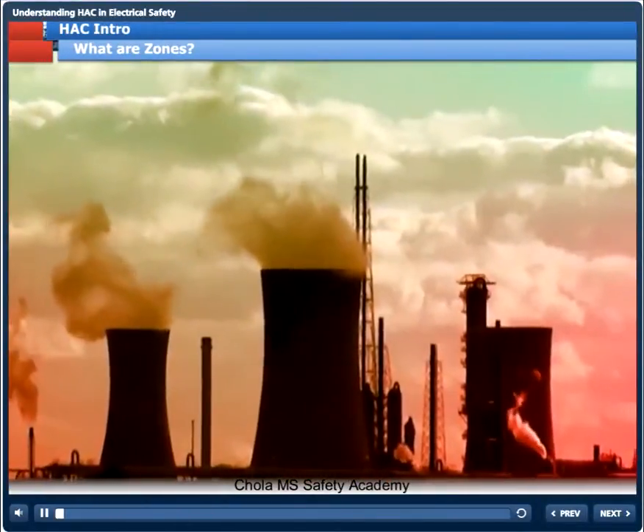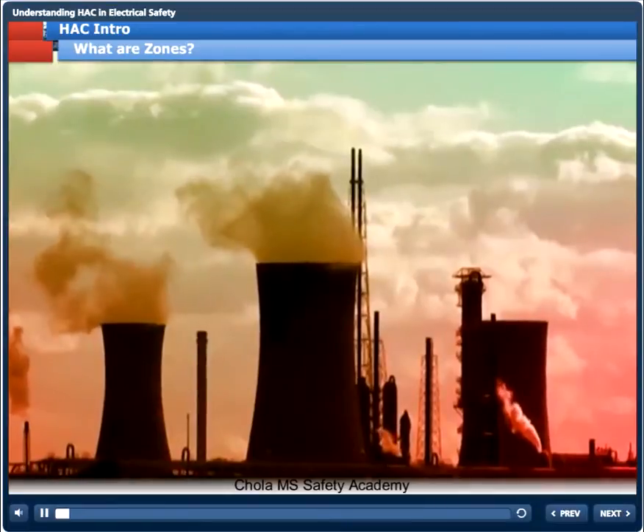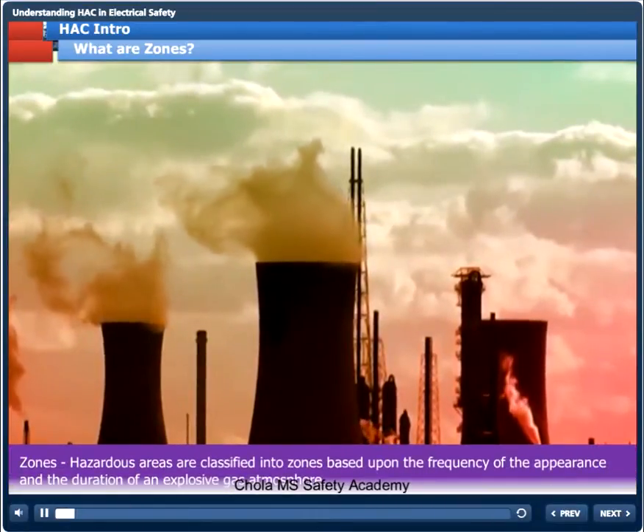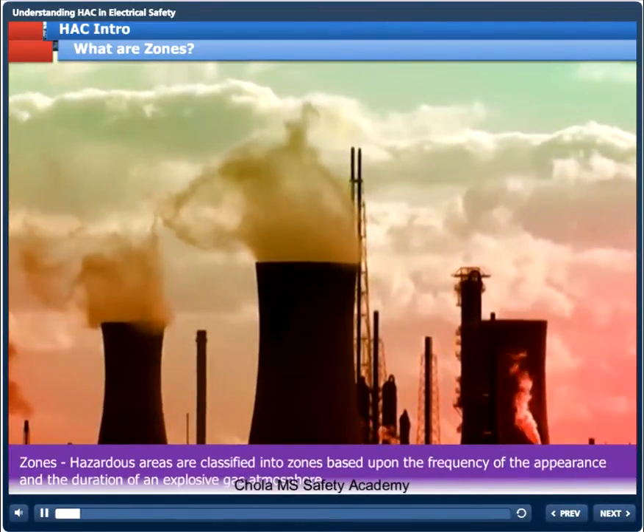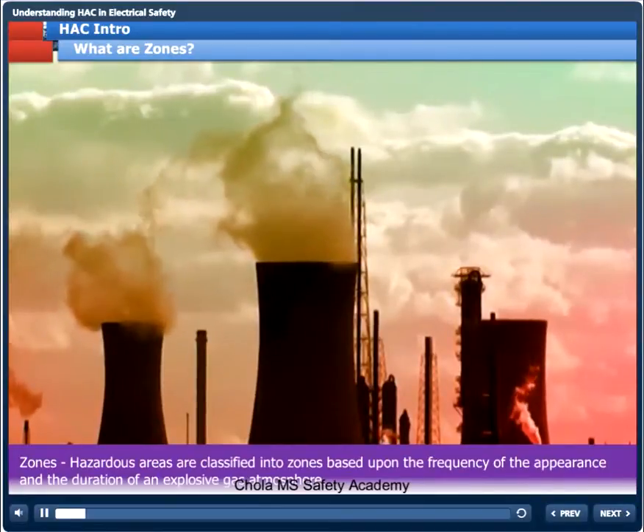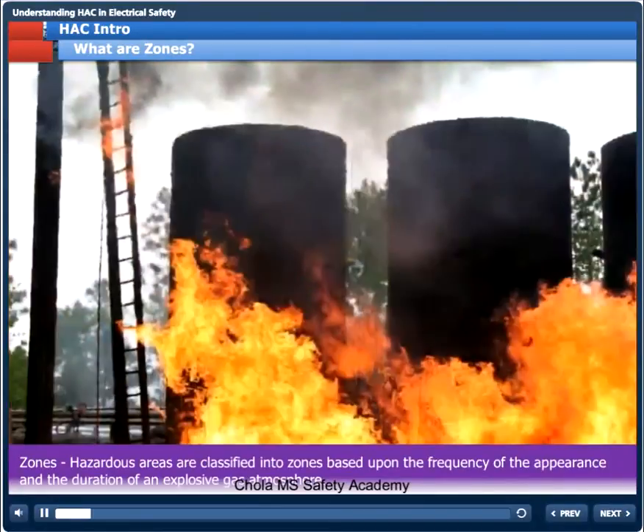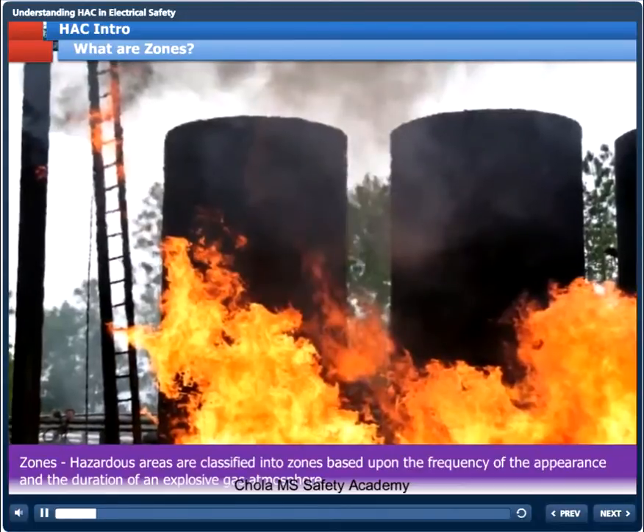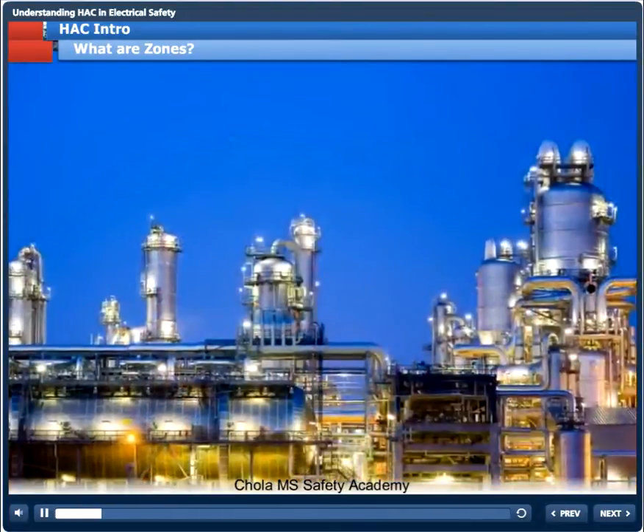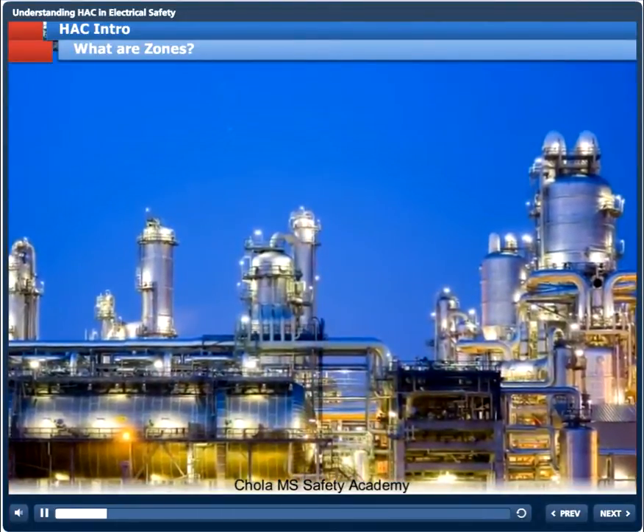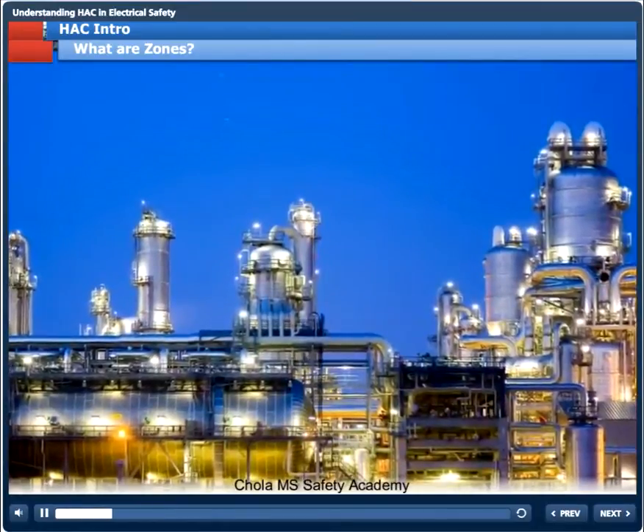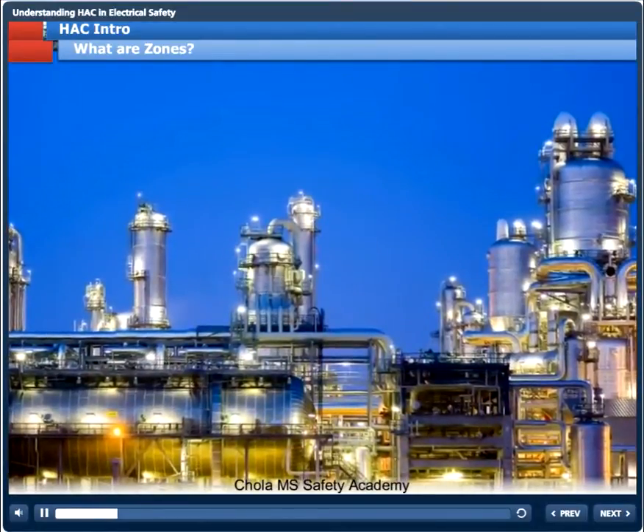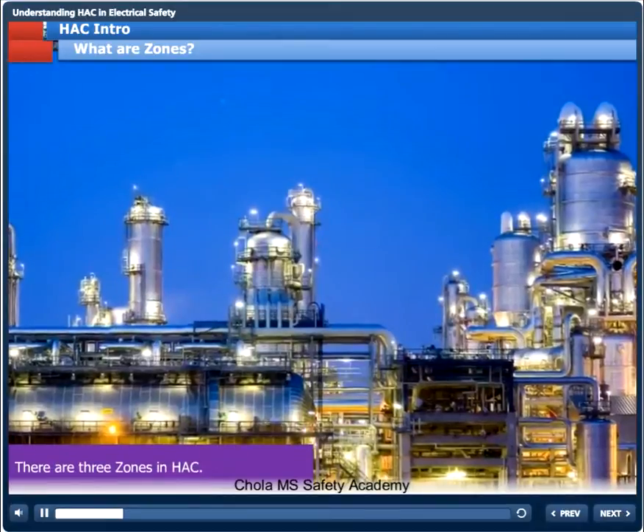What are zones? A plant which handles flammable materials is divided into zones. Hazardous areas are classified into zones based upon the frequency of the appearance and the duration of an explosive gas atmosphere. To help select the equipment, the knowledge of the zone is essential. Let us see the different types of zones in hazardous areas.